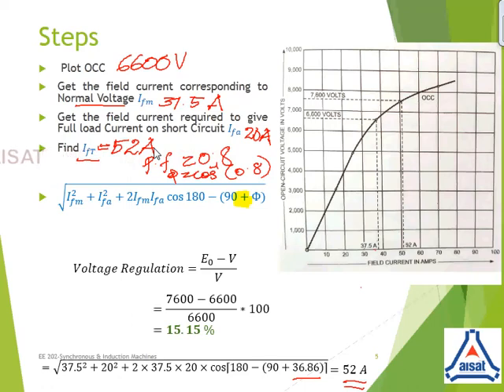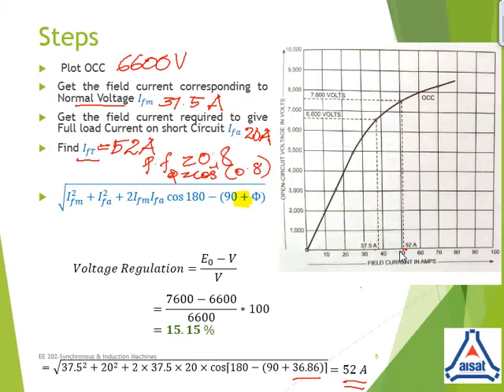Now, we need to find the no load generated EMF corresponding to that 52 ampere. Getting back to the OCC which we have plotted, corresponding to that 52 ampere, 52 ampere comes over here only. Corresponding to that 52 ampere, you erect a perpendicular such that it will intersect your OCC at one particular point. And, see that voltage value over here in the Y axis, it is making it as 7600 volt. That makes your E0 value 7600 volt.